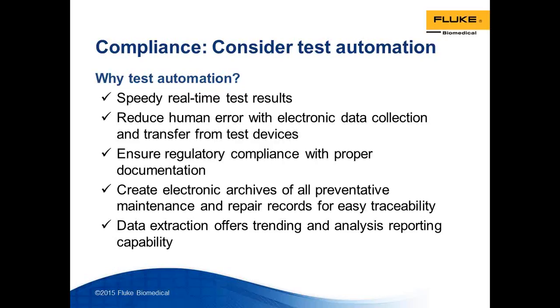The third is you are essentially complying with the requirements around proper documentation, because now the analyzer is creating a consolidated report. Everything you need to document, including who tested it, when it was tested, and the overall pass-fail, including any data requirements determined by your individual groups, are all in one consolidated report, which is then archived. And finally, you get the means to do trending and analysis if that's something you need to do to look at a certain type of infusion pump and its performance.